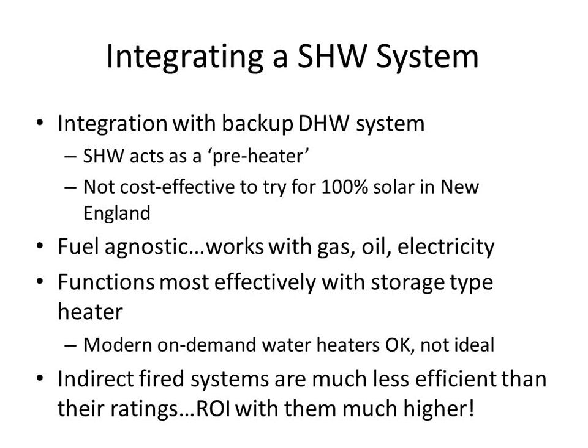Because basically what we were seeing was we were burning a lot more oil or gas in these indirect systems in the summertime than the domestic hot water energy needs calculated out to be. And after looking at 4 or 5 homes and realizing that this wasn't a measurement error, we saw this in every home that we monitored that had hot water heated with an indirect system, it finally dawned on us that for every BTU you use to heat your hot water, you're using another BTU just to heat your boiler and its water circulation system.